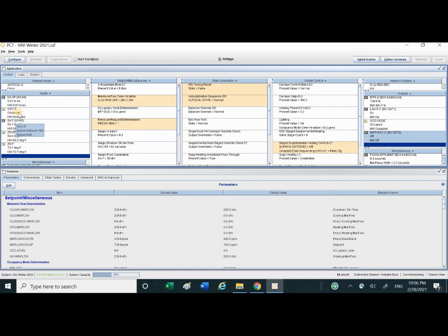Right now, we cover the occupancy sensor. So the occupancy sensor should go back to unoccupied. So I cover it, then the occupancy sensor will be delayed some time, maybe around 5 minutes, and then becomes unoccupied. So this is the commissioning process.